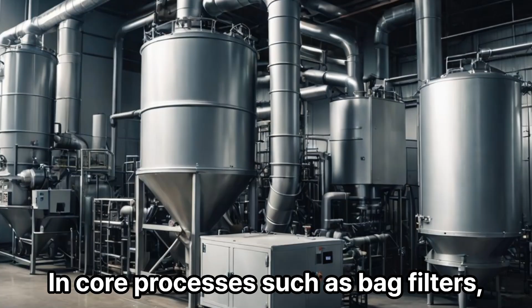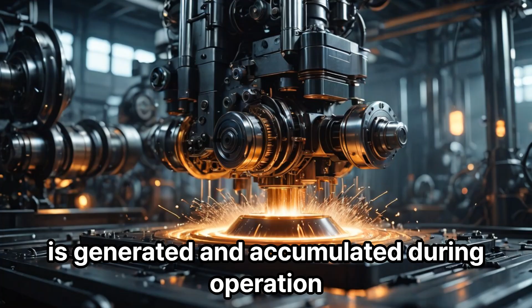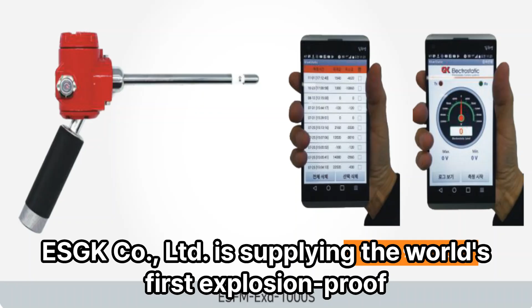In core processes such as bag filters, silos, packers, and RTOs, massive static electricity is generated and accumulated during operation. Since it is impossible to measure such static electricity, even if it seems to be operating without any issues, it can become a ticking time bomb for an explosion at any moment. However, until now, it has been impossible to measure static electricity in real time in Zone 0 during operation. Since it cannot be measured, it also could not be managed.